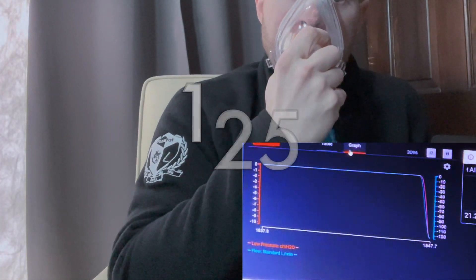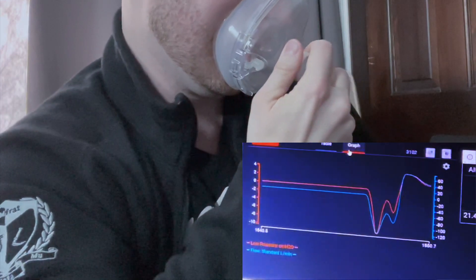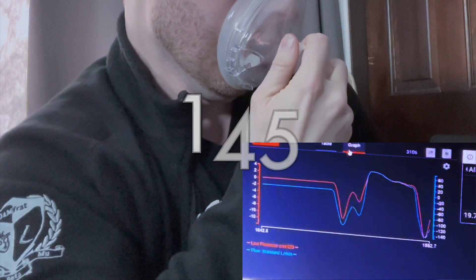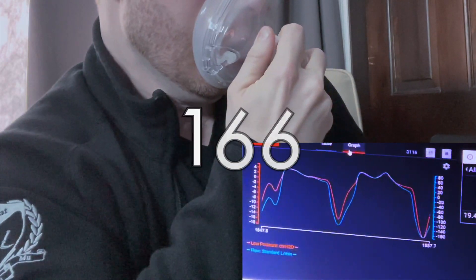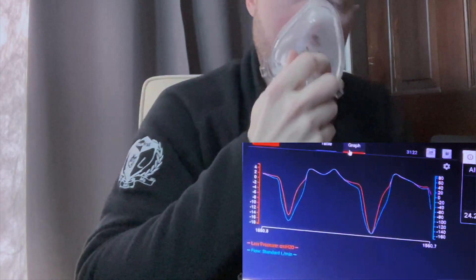All right. So now we'll see what a ridiculous flow rate looks like if somebody was super air-hungry. I don't think a patient in respiratory distress would probably be able to pull that flow rate or that pressure — maybe, I'm not quite sure. Maybe they could, but that was well over a hundred. I think it hit like 150 or 160 — those flow rates are very, very fast.